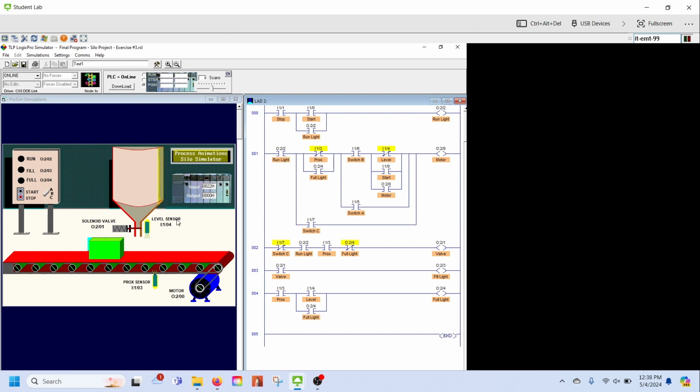The 3 modes shall operate as follows. When the selector switch is in A position, the system shall operate in the continuous mode of operation. This is the mode of operation which was used in exercise 1.